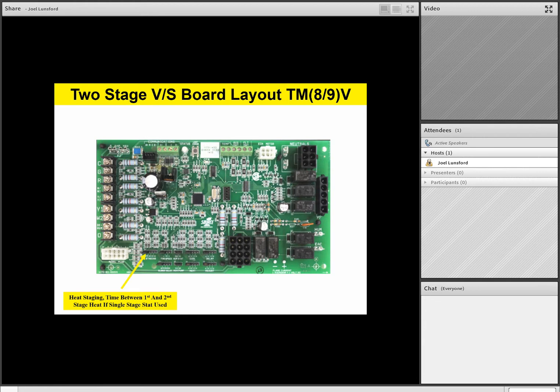Finally, the last component we have on our board is a model ID plug on the variable speed motor control. It's just a simple wired plug that tells the board what size furnace it's hooked up to. The important thing to remember is that if you sell a replacement board, or the contractor installs a replacement board, they want to make sure to take the model ID plug off the old board and snap it onto the new board, so that when they power it up the first time, the new board will know what size furnace it's hooked up to. So that model ID plug is important. It has to be installed on the board so the board knows what size furnace it's hooked up to.